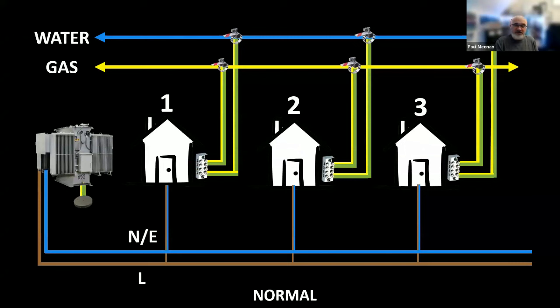So I like to do pictures. So this is a very basic picture of a substation with an earth reference. And in England, what we have is basically a combined neutral and earth in the street now, because of the age of the networks. That's what they've done. We have a live conductor, a line conductor, sorry, that goes into the house, into a cutout, and then you have an earth terminal where the water and gas will be bonded, or any extraneous services. Excuse me. So that's normal. That's how we wire things, and obviously energy goes in, goes out, back to the transformer, no problem at all. That's how it should work.